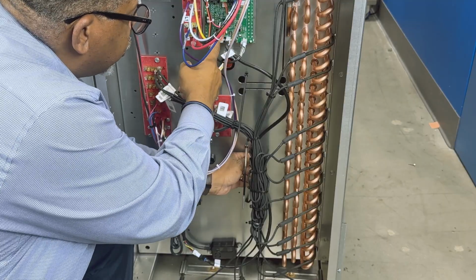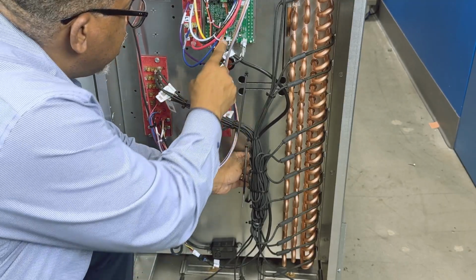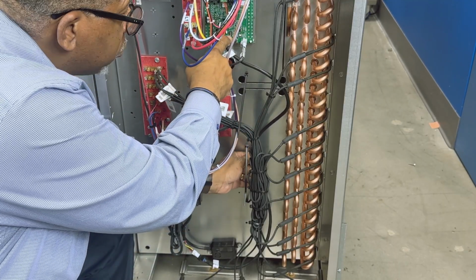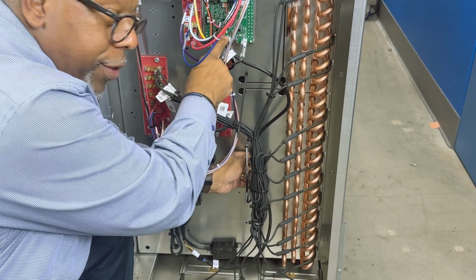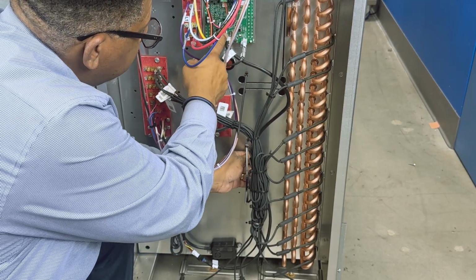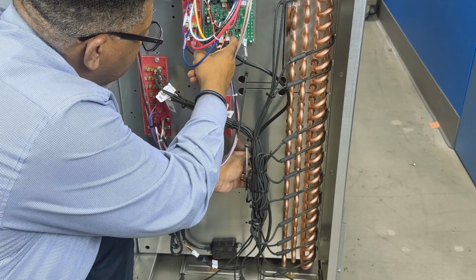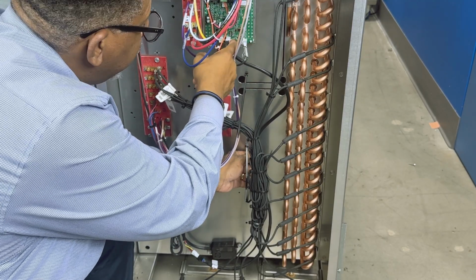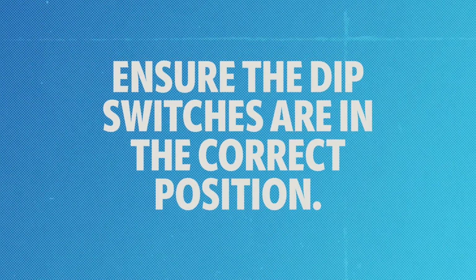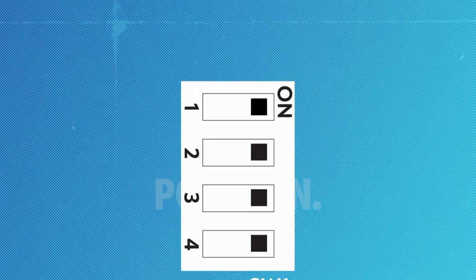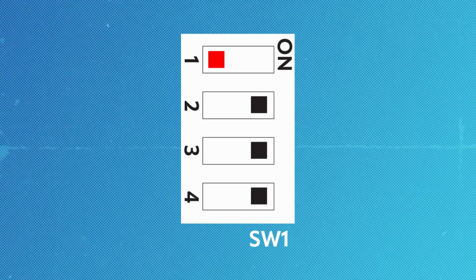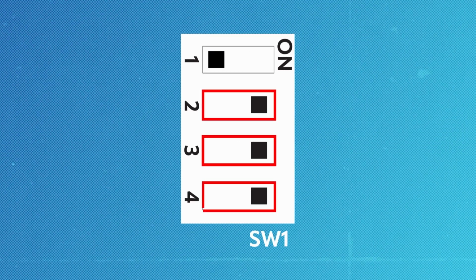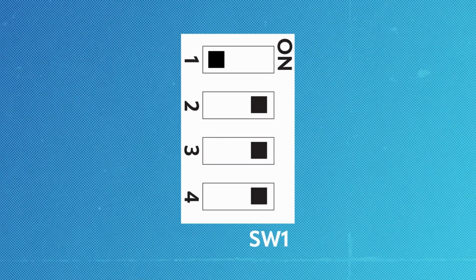We have 3 spaces here for sensors. Space number 1 is where I have this installed now. So that's why that's there. We have dip switches here. At the bottom, they're numbered from 1 to 4. Once the sensor is connected, you'll need to ensure the dip switches are in the correct position. The first dip switch should be set to the off position. The rest of the switches should now be located in the on position.